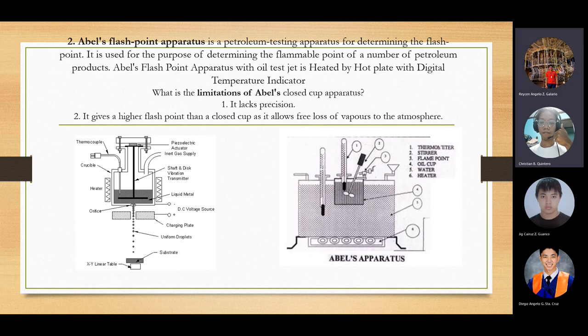This is the example we showed earlier. Abel flashpoint is a petroleum testing apparatus for determining flashpoint. It is used for determining the flammable point of a number of petroleum products. Abel flashpoint apparatus with oil test jet is heated by hot plate with digital temperature indicator. There's a small slider with an opening that can be opened and closed. Light the matchstick and bring it close. Then we can see if there's flashpoint or firepoint.